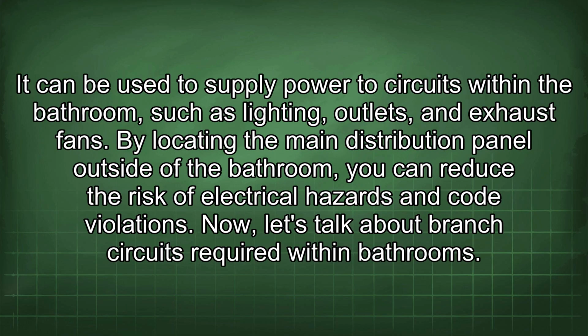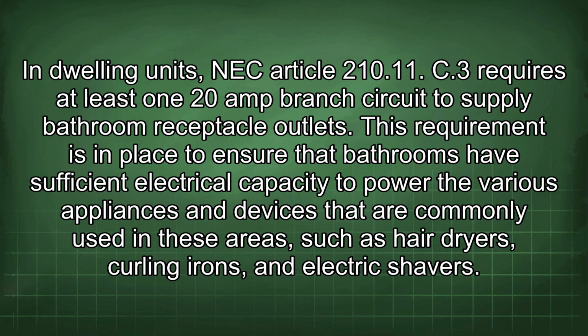It can be used to supply power to circuits within the bathroom, such as lighting, outlets, and exhaust fans. By locating the main distribution panel outside of the bathroom, you can reduce the risk of electrical hazards and code violations. Now let's talk about branch circuits required within bathrooms. In dwelling units, NEC Article 210.11(C)(3) requires at least one 20-amp branch circuit to supply bathroom receptacle outlets.